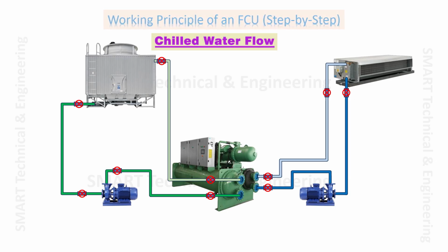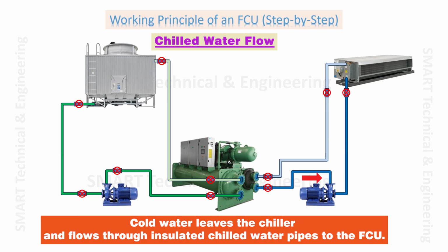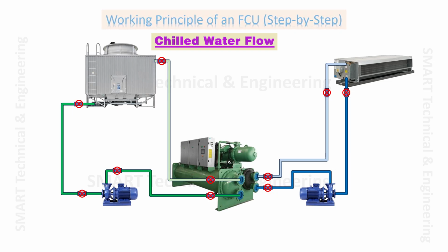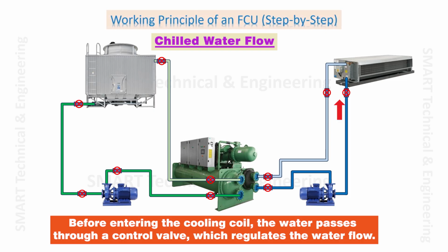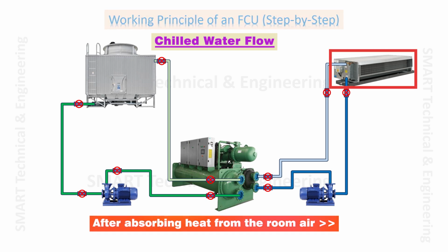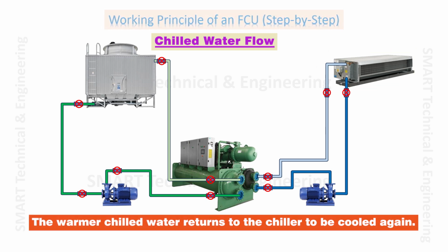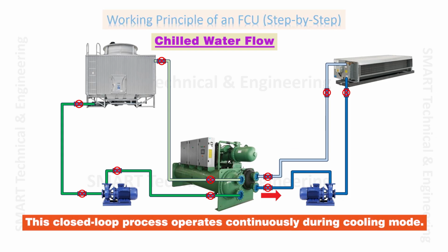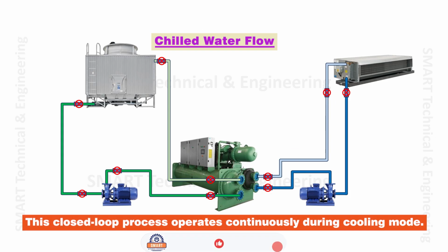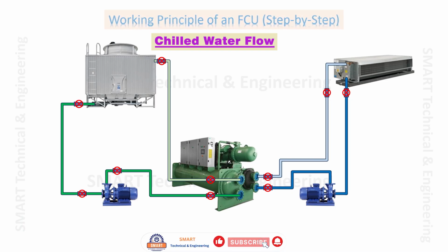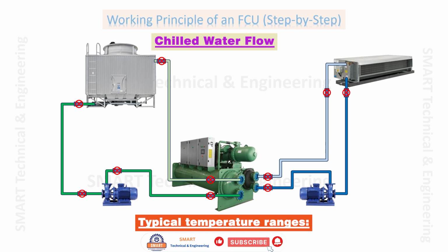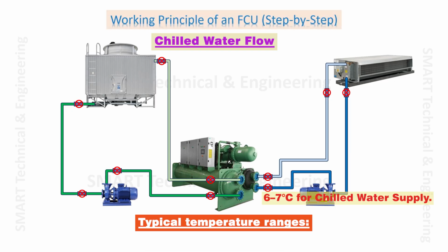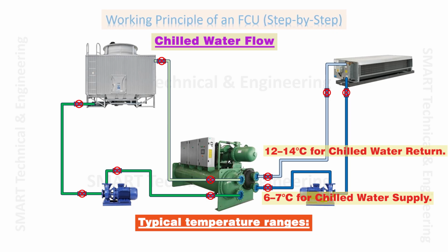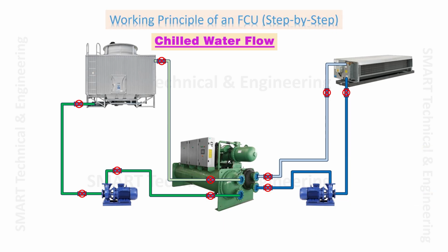Chilled water flow. Now let's examine the chilled water circuit. Cold water leaves the chiller and flows through insulated chilled water pipes to the FCU. Before entering the cooling coil, the water passes through a control valve, which regulates the water flow. After absorbing heat from the room air, the warmer chilled water returns to the chiller to be cooled again. This closed-loop process operates continuously during cooling mode. Typical temperature ranges are as follows: 6 to 7 degrees Celsius for chilled water supply, 12 to 14 degrees Celsius for chilled water return.